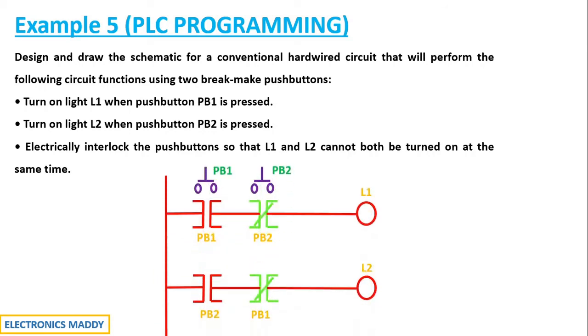Now let us consider another example. If I initially press PB2 what happens? This will actually get turned on and this will get de-energized because this is a normally closed contact which was acting as short circuit before and because of its energization it becomes an open circuit. So we're using the same addresses over here and here. Normally the addresses will be indicated as I.2 slash O depending upon the type of PLC controller that you're using. But as a whole I'm using names just for easier to understand these type of concepts. So now once this is done if you carefully observe both the contacts are turned on so the entire rung will be energized. Current starts flowing from the source to the load and the light L2 will actually turn on. Even if you press PB1 now this is acting as open circuit so the state will not change. As a result L1 will not turn on.